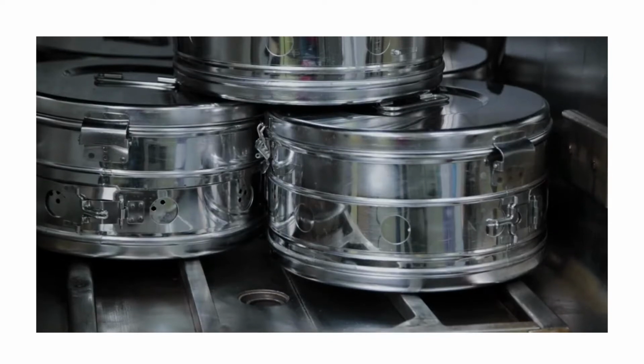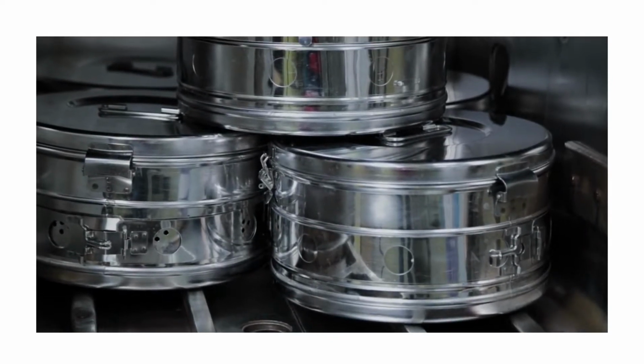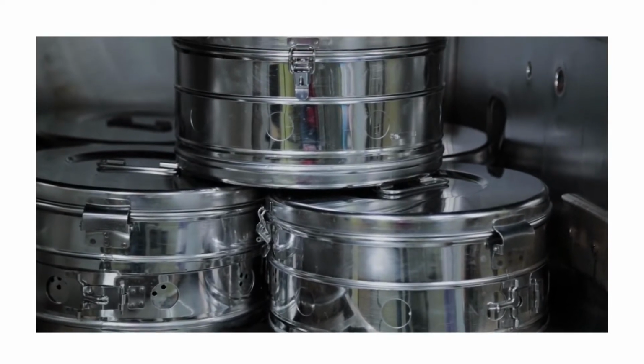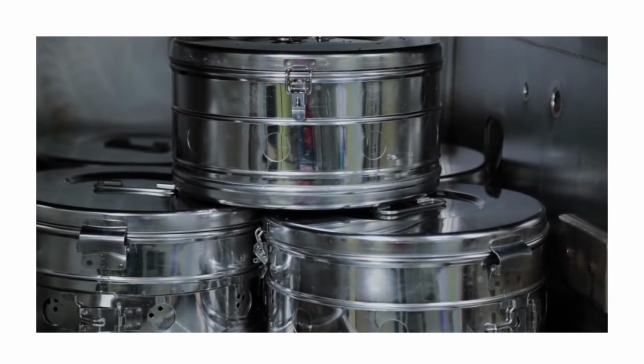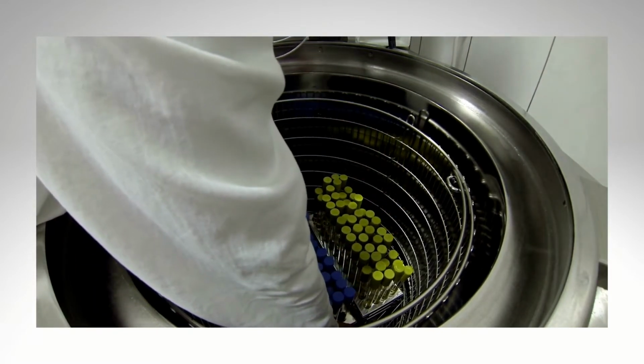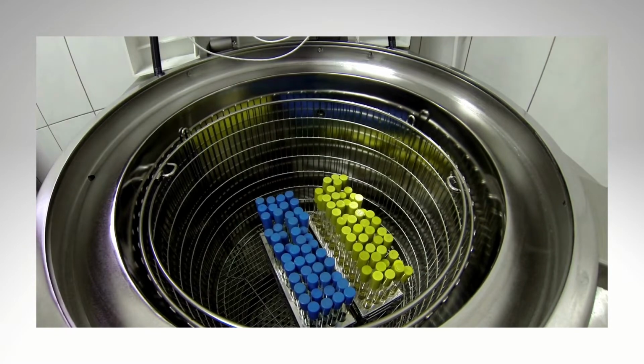Sterilization with steam under pressure is done with autoclaves. Pressure serves as a means to obtain the high temperatures necessary to quickly kill microorganisms. Specific temperatures must be obtained to ensure microbicidal activity. The two common steam sterilizing temperatures are 121 degrees Celsius and 132 degrees Celsius.